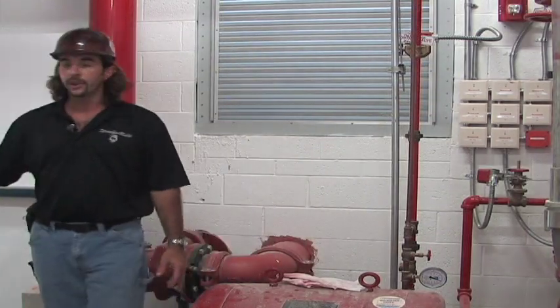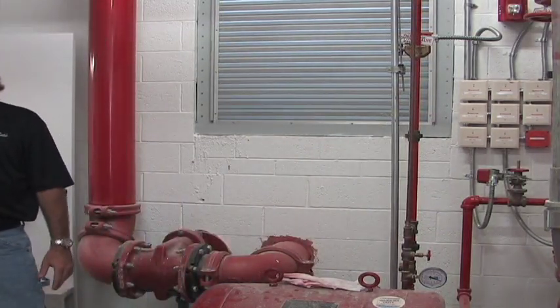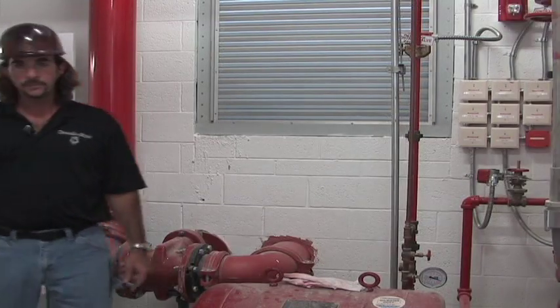Today we're going to go through the basic operation of an electric fire pump. We're going to run through the maintenance, and we're going to run through the startup and shutdown procedures of a fire pump. What we have here today is our electric fire pump. We're going to go through all the different valves that work this fire pump. We've got a maintenance pump, which is going to be considered as our Jockey pump. We're going to have our Jockey pump controller, and we're going to have our fire pump controller. We're going to run through all these different tests.